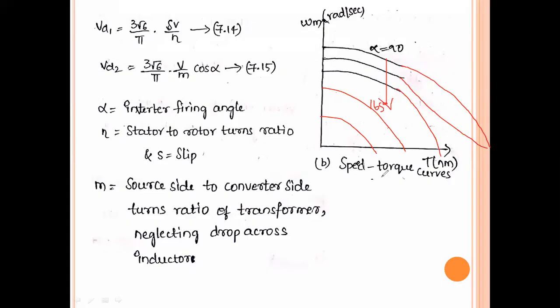Also, where the speed range is very narrow, like a minimum speed of 1300 and a maximum speed of 1500, you can observe the difference in this speed range is very narrow, around 200 RPM. In applications with a narrow speed range, like fans, pumps, blowers, those types of industrial applications, we can develop this static Scherbius drive.